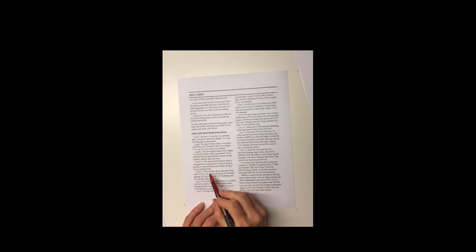For the window type, again, we're going to look at, on this table, for line 5, it says the window area is the area of the sash, so we're going to use R1 for single glazing, R2 for double glazing, R3 for triple low E glazing, and R4 for heat mirror.